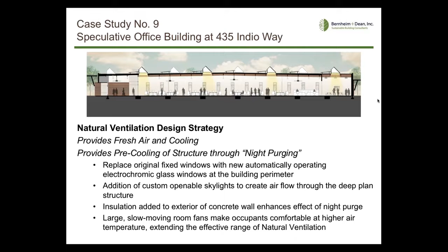And they did this by retrofitting the fixed windows, and obviously you need to do that if you're going to naturally ventilate the building. The windows are automatically operating and controlled by the central system. They added roof monitors with exhaust vents built in, so you could get cross ventilation. When you have a big floor plate, it's important to get the air to move through the intermediate rooms. They used air transfer ducts for that, and the designers had distributed HVAC units for the mixed mode operation. I'll explain a little bit about that.